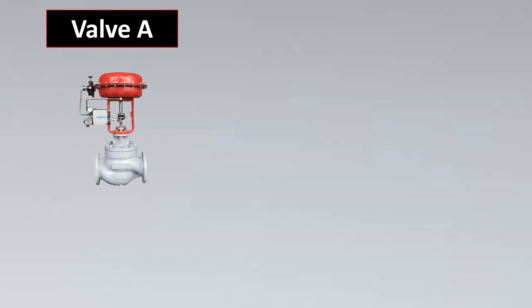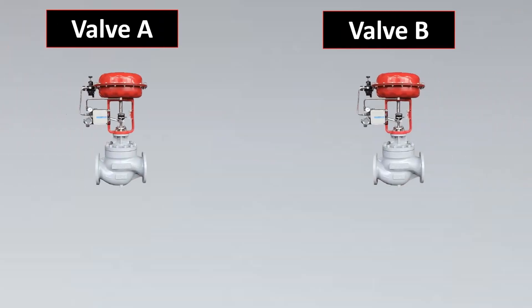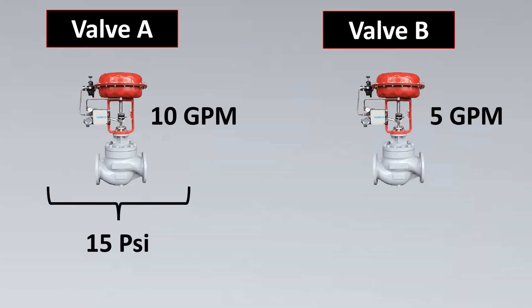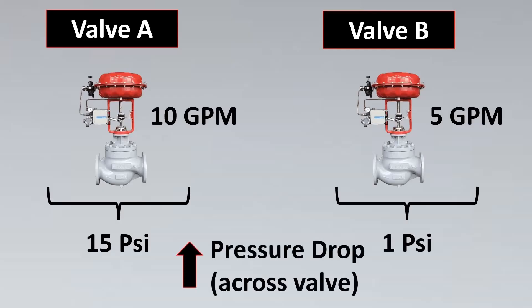As we had initially discussed, imagine valve A has a flow rate of 10 GPM and valve B has a flow rate of 5 GPM. We cannot say that valve A has a higher flow capacity, because both valves could be made of the exact same construction and same size, but the pressure drop across the first valve is 15 PSI while the pressure drop across the second valve is just 1 PSI. As you increase the pressure drop across a valve, the flow through it increases — so this higher flow is due to pressure drop, not valve size.